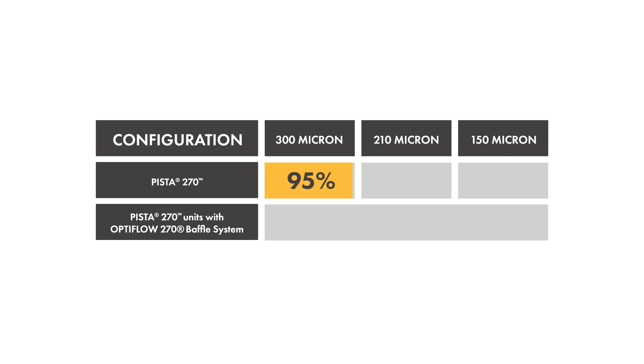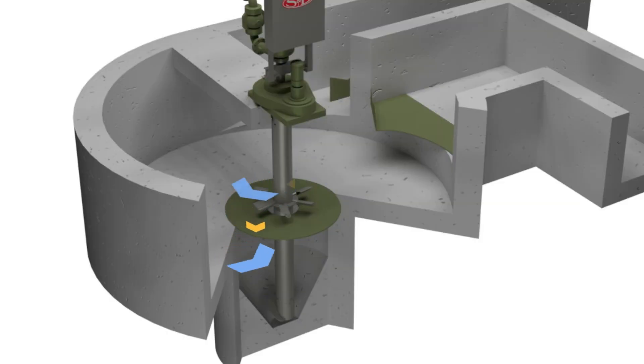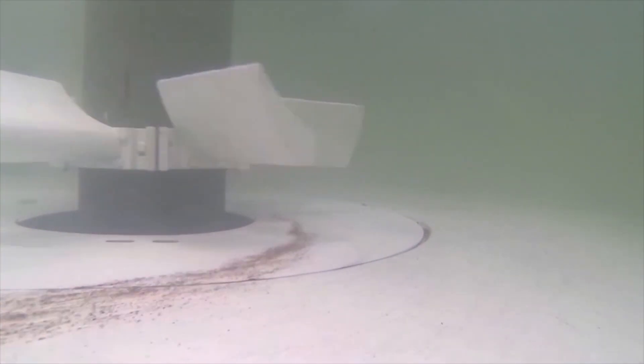The OptiFlow baffle creates a forced vortex that allows 95% grit capture of 150 micron grit at all flows. The axial flow propellers sweep grit along the floor in a moving bed towards the hopper opening and also lift organics back into the flow to continue moving them to the next stage of treatment.